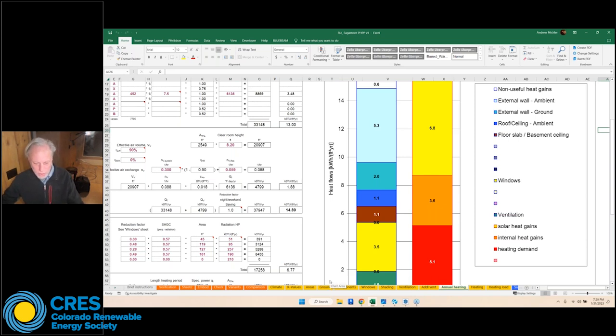The other side, of course, is ventilation and fresh air. I didn't get into that in the fire talk, but it's one of the critical aspects of Passive House and fire: that airtight envelope means you put in a ventilation system with a heat exchanger, a heat recovery ventilation system, so we can actually filter the air coming into the home, providing another way of protecting occupants from smoke, which is a significant issue now in the summertime, but also from particulate matter and things like that. Air quality is getting significantly worse through the years.